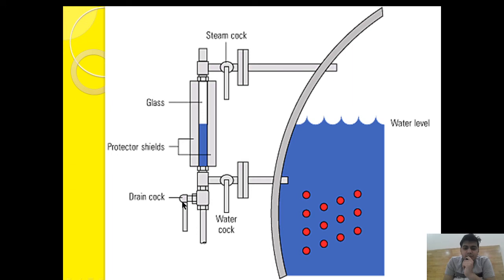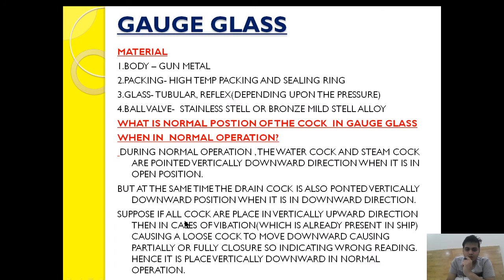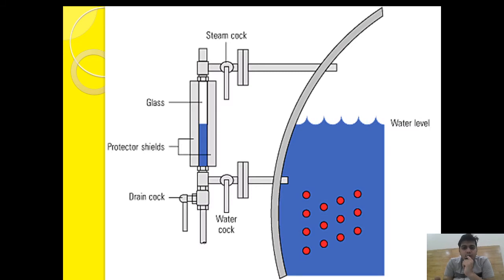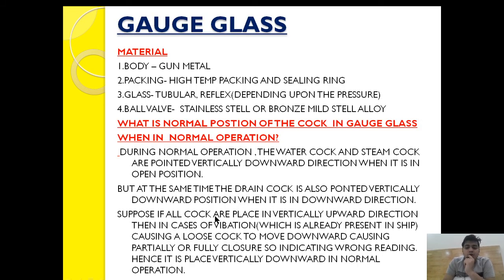The drain cock in the vertical downward position is in closed condition. So remember: the steam cock and water cock pointing vertically downward are open, but the drain cock pointing vertically downward is closed. During normal operation, the water cock and steam cock are pointed vertically downward when in the normal open position, while the drain cock is also pointed vertically downward when in the closed position.